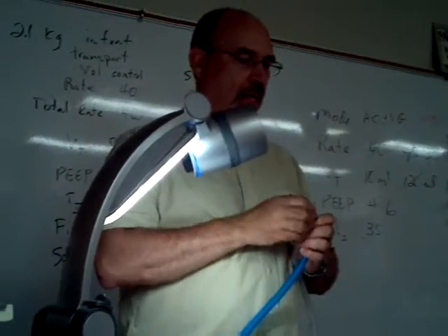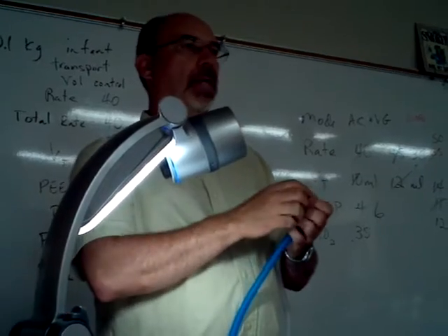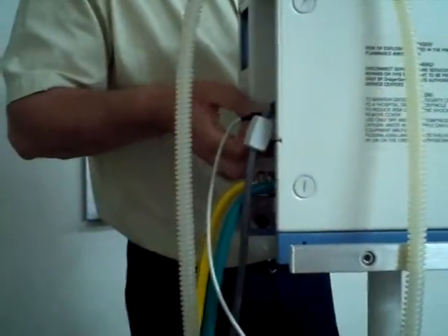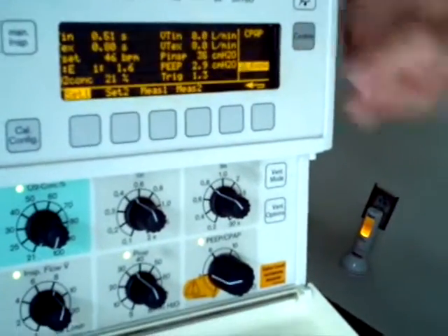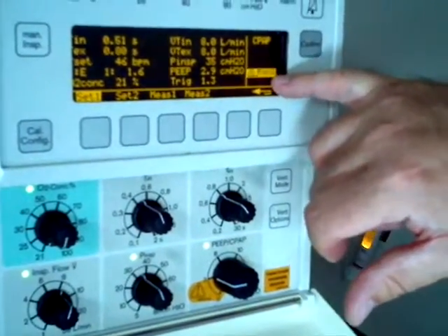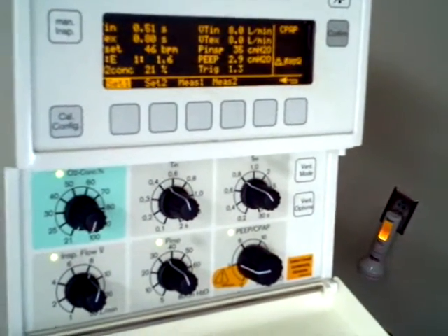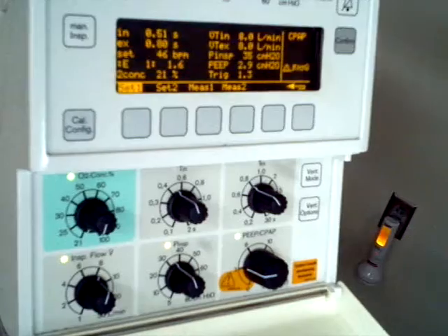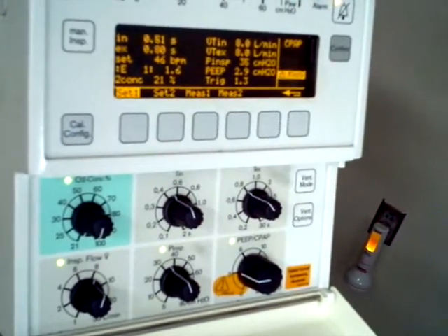Put on our nasal prongs, okay, for the baby. And we're also going to unplug the flow sensor in the back. Sorry, Jason. There we go. Okay? We're basically going to dumb down the machine, if you will. Now it's going to say flow measurement disturbed. So a lot of stuff we were using is no longer going to be available. We just confirm it. Notice it says there's no flow sensor in there. Turn all your alarms on too. Well, they'll automatically go off; that's why you want to unplug it in the back. Otherwise, you'll get alarms continuously.